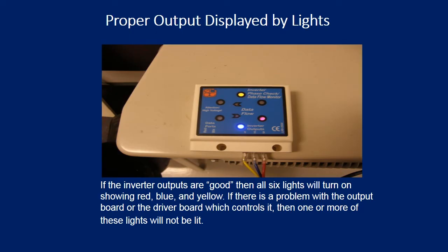If the inverter outputs are good, then all 6 lights will turn on showing red, blue, and yellow. If there is a problem with the output board or the driver board which controls it, then 1 or more of these lights will not be lit.